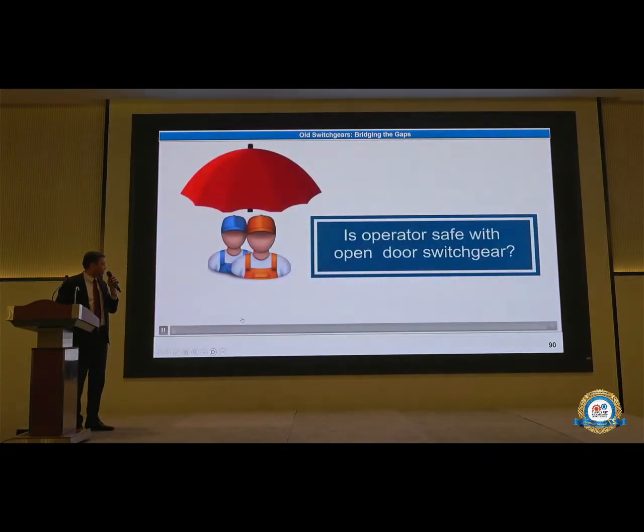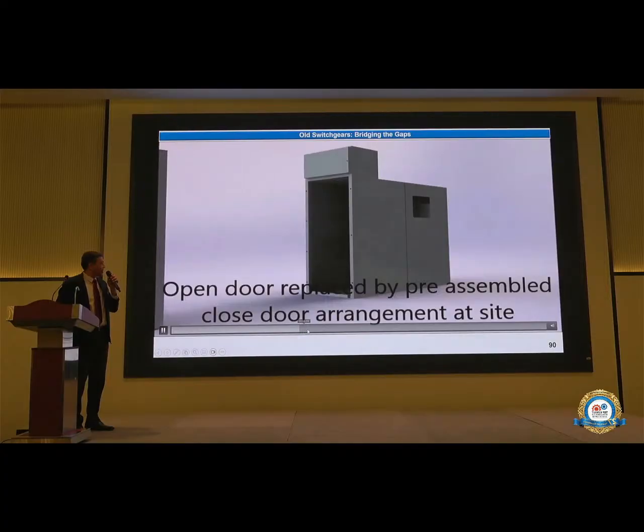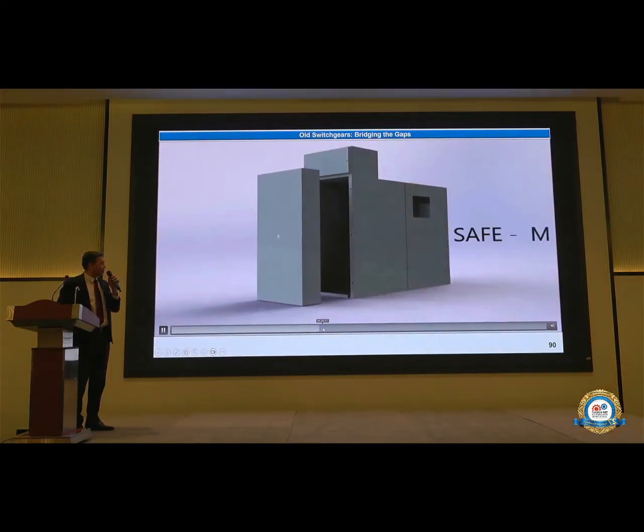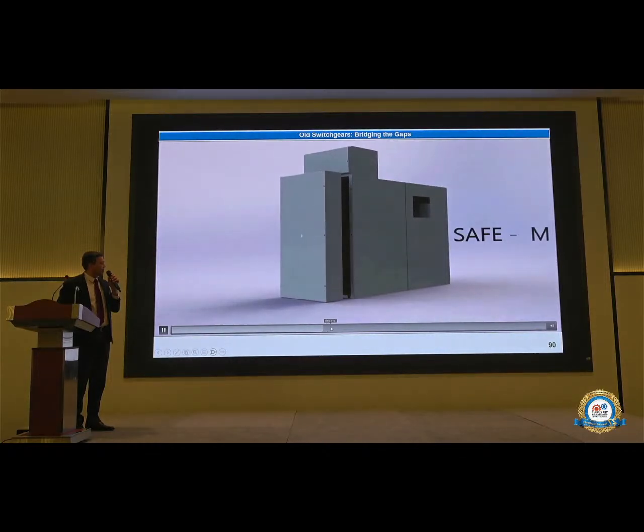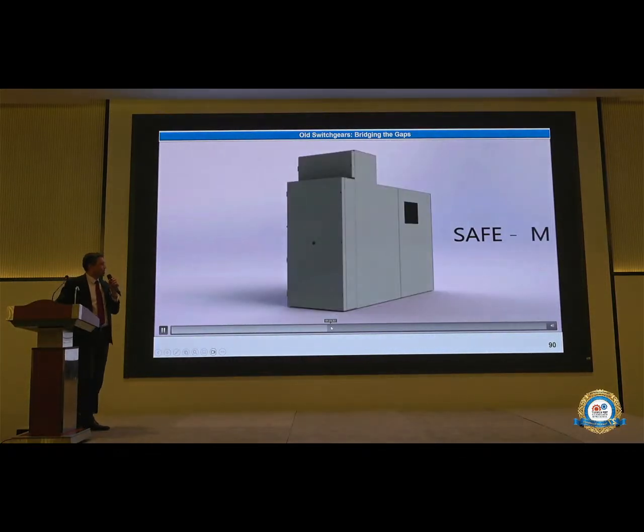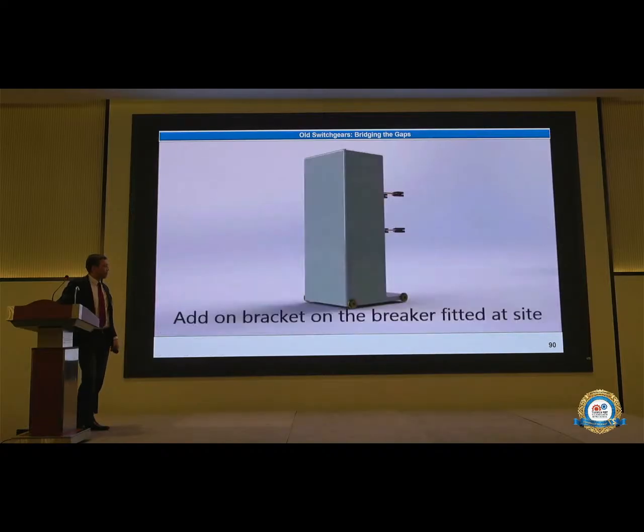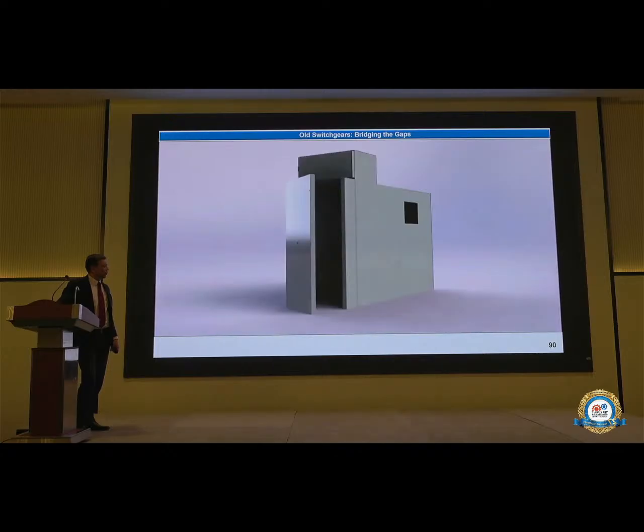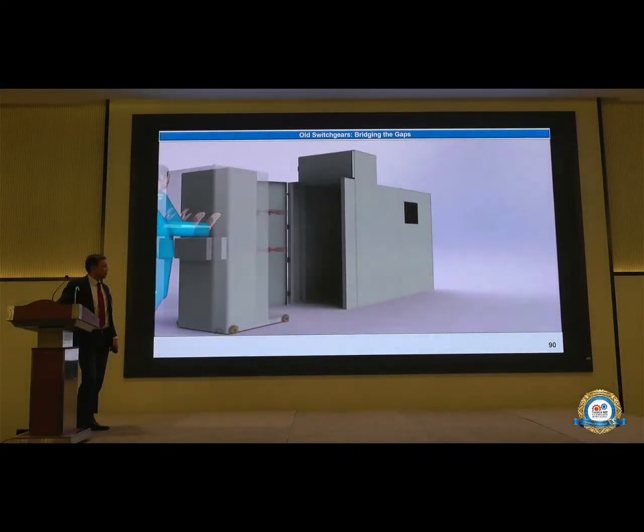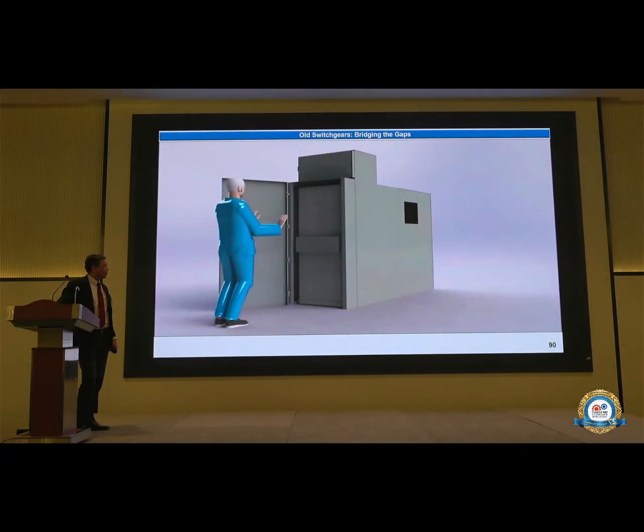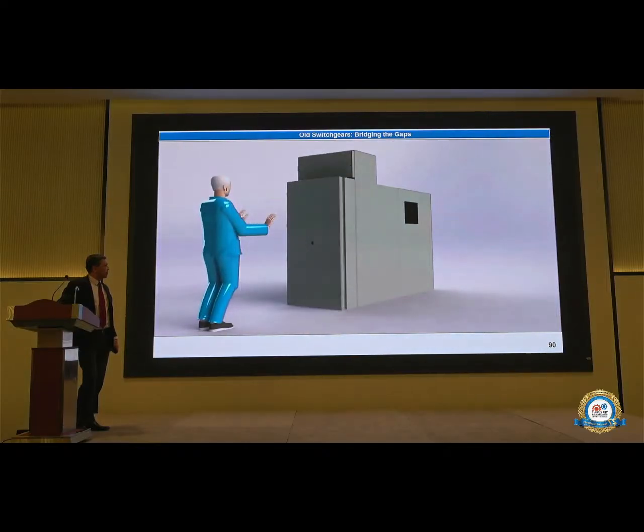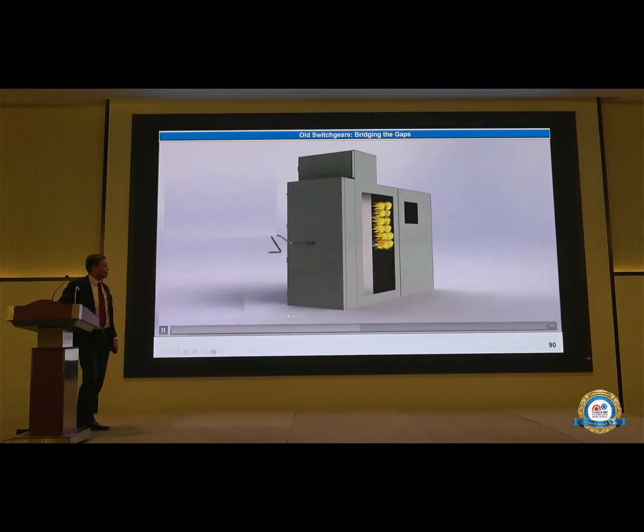Can the operator really be kept safe by replacing the open door with what we call a safe module or safe end? This can be fitted to any existing switchgear with minimum changes to the breaker. With the SAFE-M, the operator is always safe behind the closed door racking arrangement. Even racking can be done by a motorized arrangement where the operator need not be near the switchgear at all.